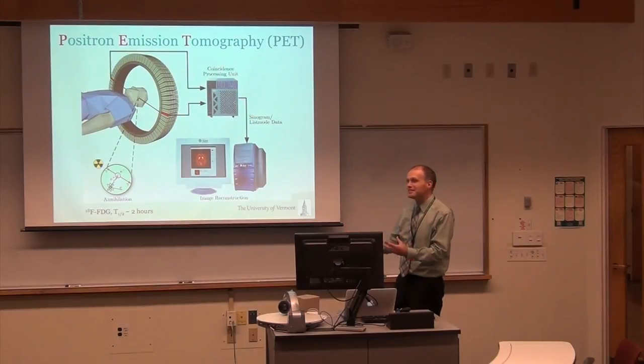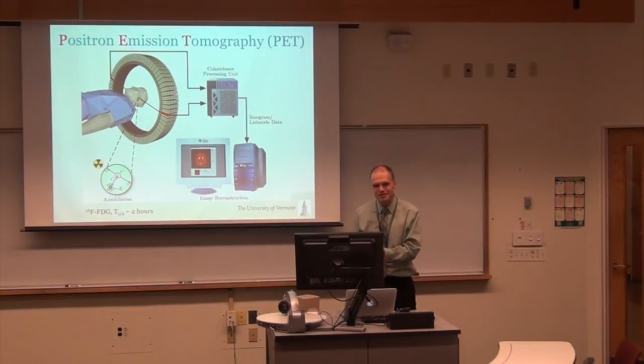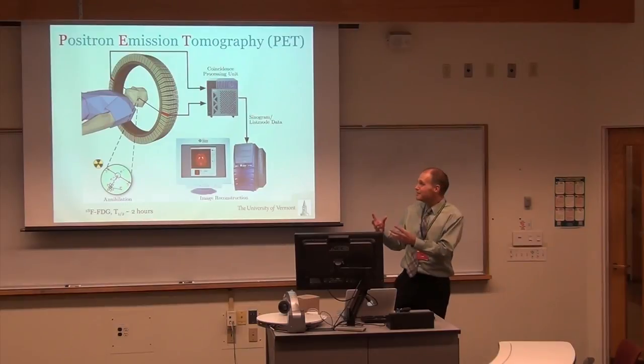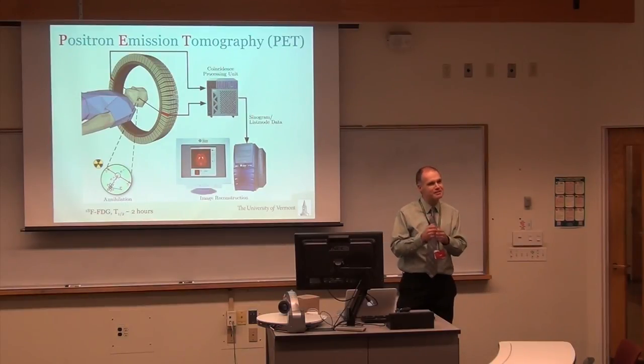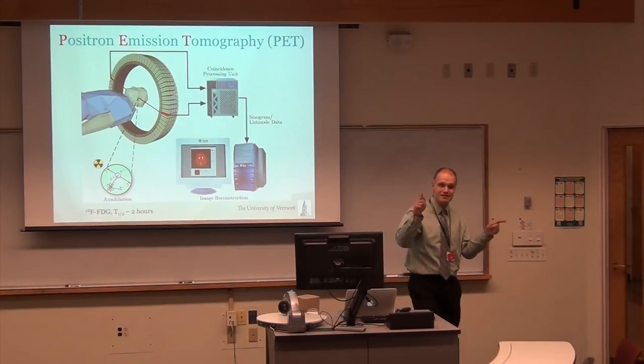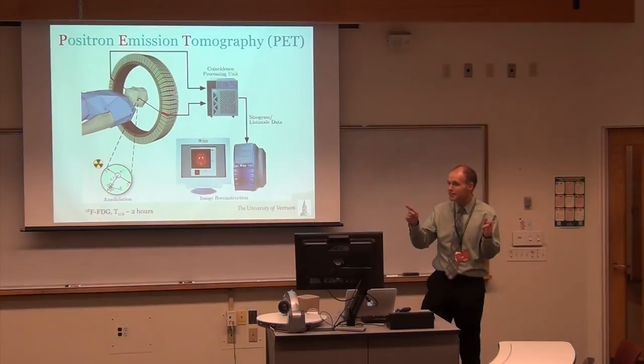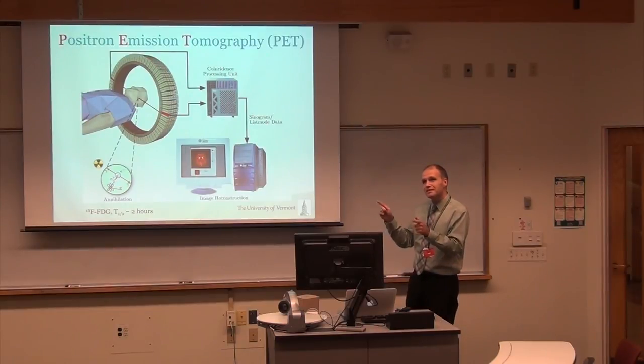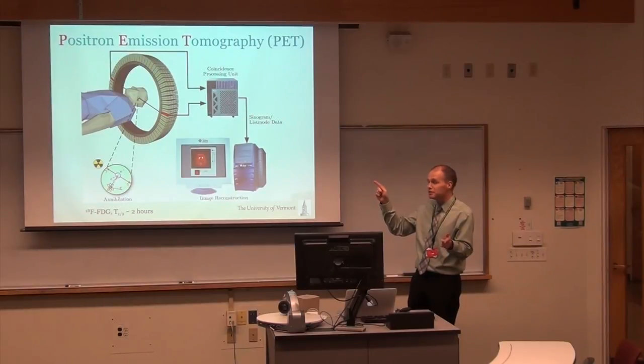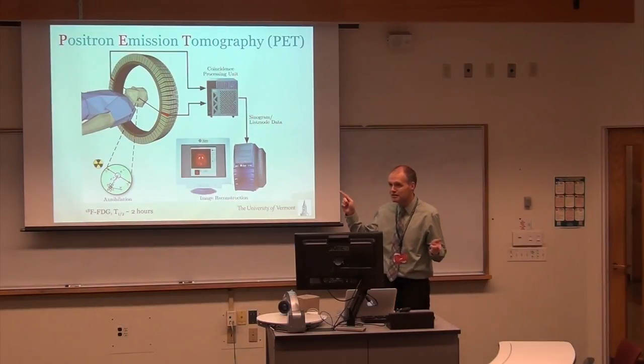So positron emission, positron-electron annihilation. Now you have two photons generated in the same event at the same time, going in opposite directions. If I have detectors and I detect those two photons at the same time, then I know that annihilation event happened on a line connecting those two detectors. That's positron emission tomography.